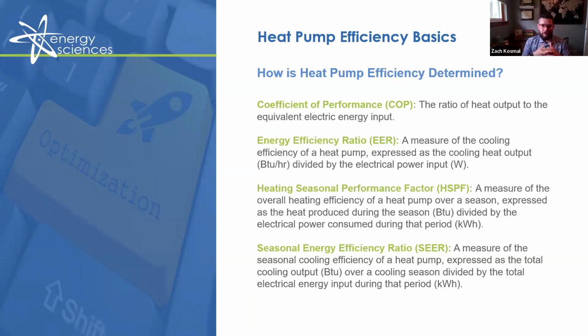So you can see how that efficiency is extremely impactful, and we'll get into why that is a little bit down the road. Ground source heat pumps range between 3 to 5, and then water source heat pumps range from 3 to 5.5.